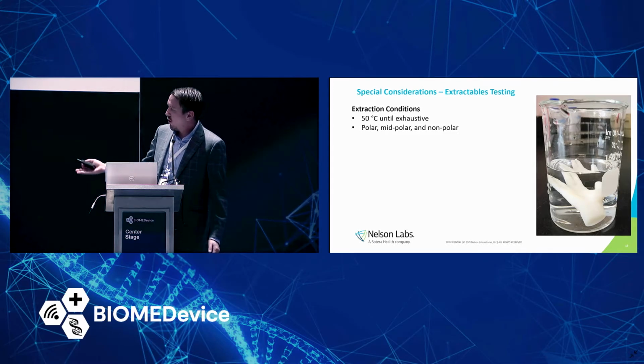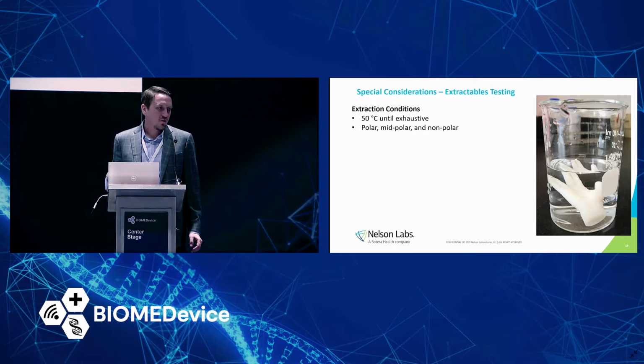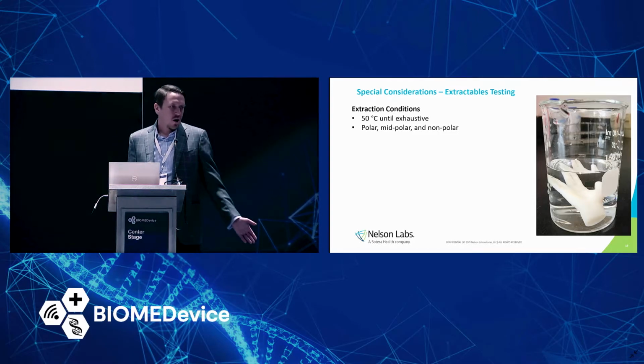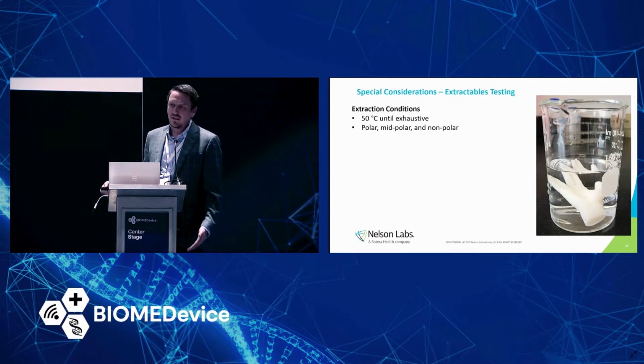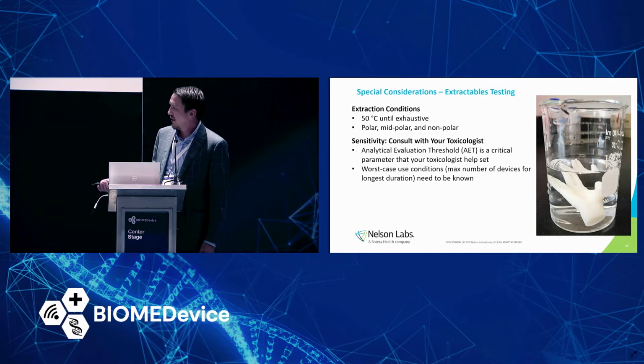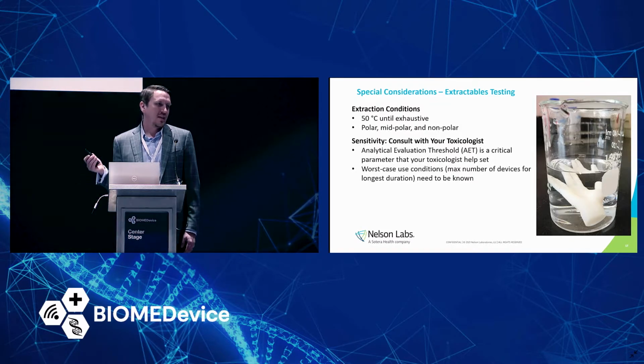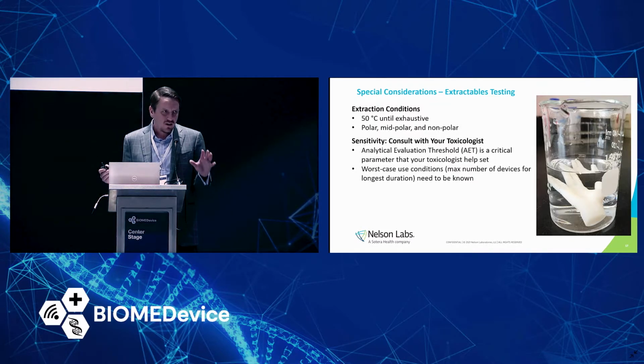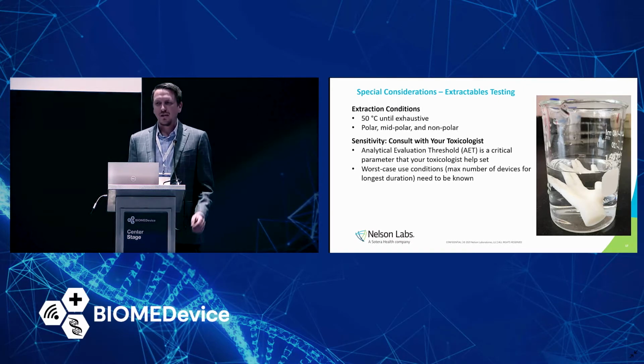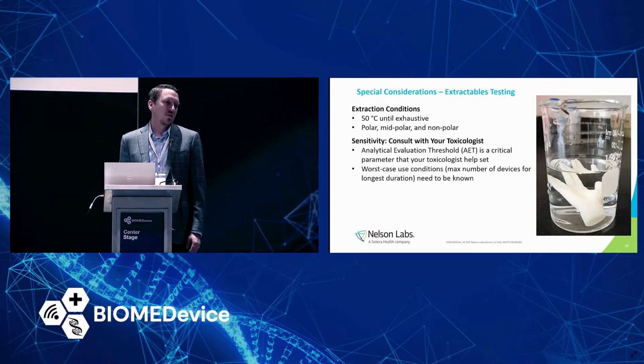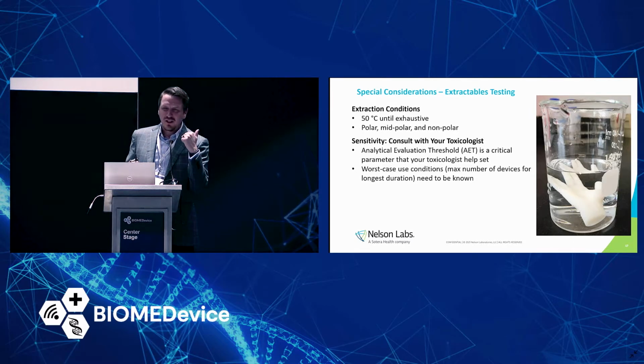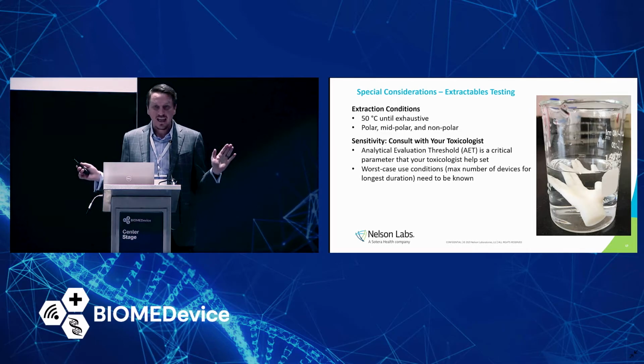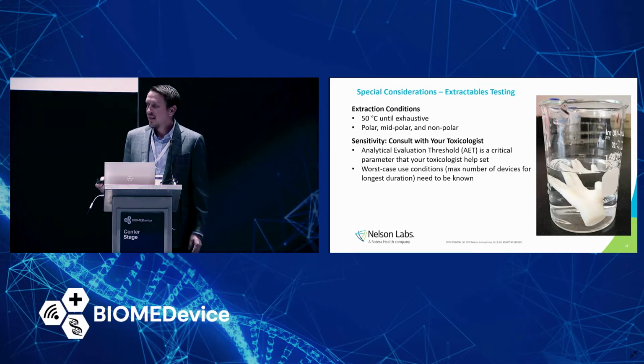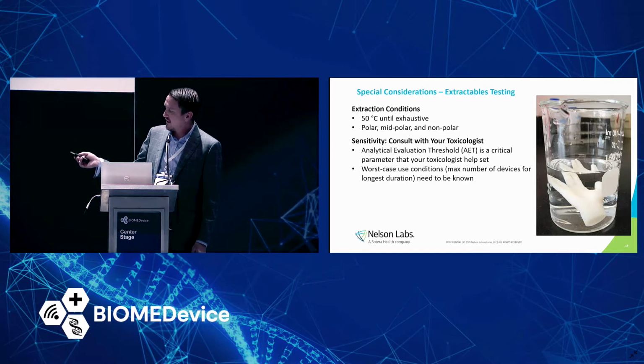So if it's prolonged or long-term, it's got to be 50 degrees C until exhaustive with a minimum of 3 solvents. You can't compromise on that. Even if these conditions don't make sense, you still have to do these conditions and then do something else after. The sensitivity to the FDA is very, very important. So the sensitivity of this chemical analysis can be an absolute deal breaker. I've seen and been on calls with the FDA where this was the factor that kept a device from the market at the very, very end. They said, sorry, that AET was just not quite low enough. And that's it, case closed. Let's retest and resubmit. So the sensitivity of analysis is super important.